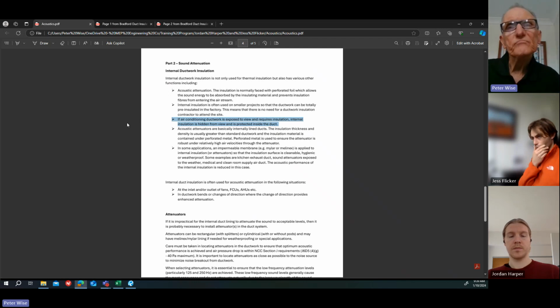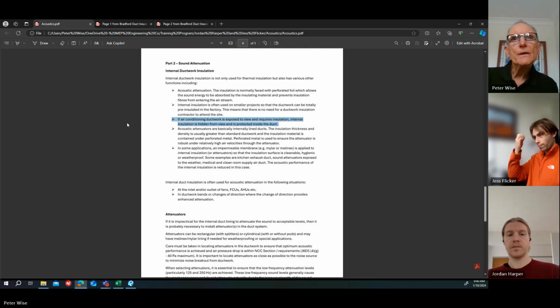Sometimes you'll have this in, say, a bulky goods store or a shopping centre where the ductwork has to be insulated, but it's exposed to view. So you're better off to internally insulate it because then you can't see it, it's protected, and it gives a better finish. Also in plant rooms, ductwork is normally internally insulated for protection and for acoustic benefits.